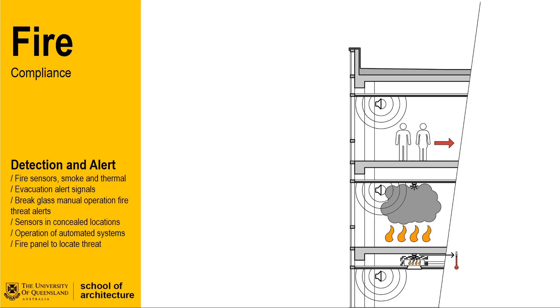There are also break-glass type fire threat alerts that are manually operated by the building occupants. Once a fire is detected, it activates the fire safety systems. This may trigger the closing of fire compartment doors and the sounding of an alert signal informing the building's occupants to evacuate the building. Most detectors in a Class 2 to 9 building will be on a network that is collated to a central fire panel, which will provide a location of the source of the threat for firefighters entering the building.